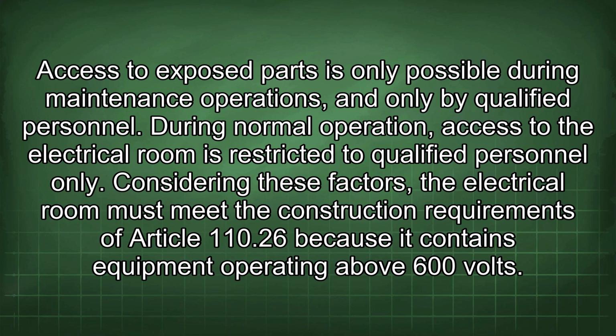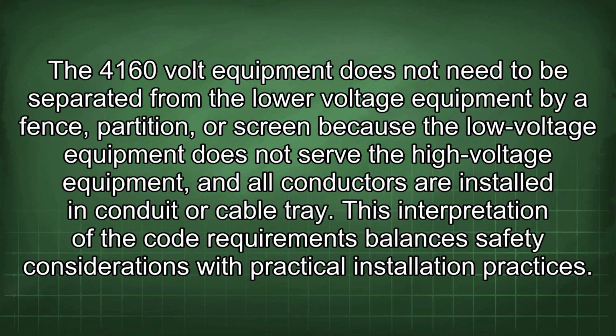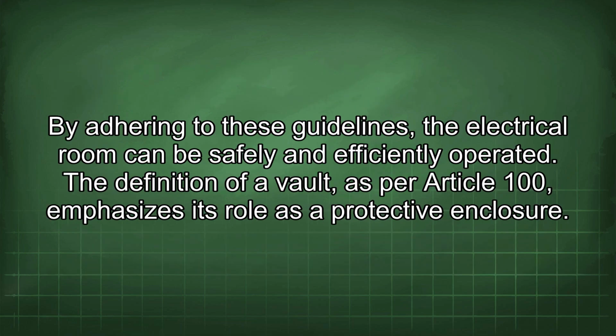Considering these factors, the electrical room must meet the construction requirements of Article 110.26 because it contains equipment operating above 600 volts. The 4160-volt equipment does not need to be separated from the lower voltage equipment by a fence, partition, or screen because the low voltage equipment does not serve the high voltage equipment, and all conductors are installed in conduit or cable tray. This interpretation of the code requirements balances safety considerations with practical installation practices. By adhering to these guidelines, the electrical room can be safely and efficiently operated.